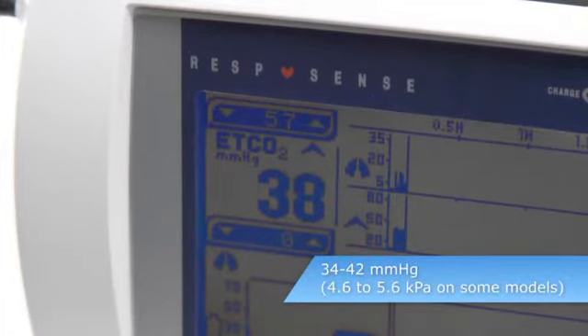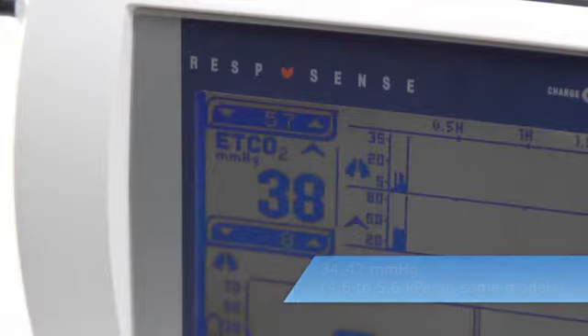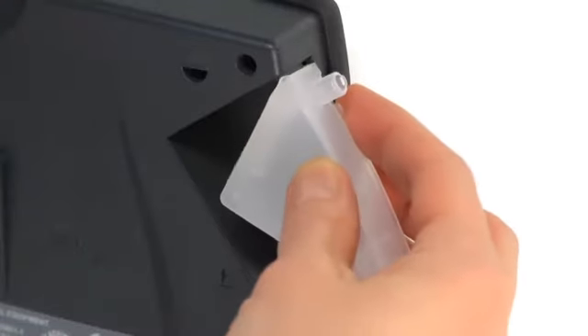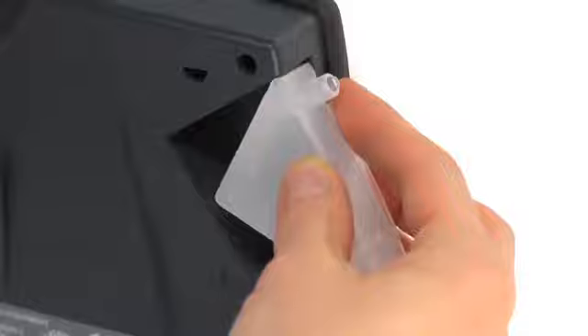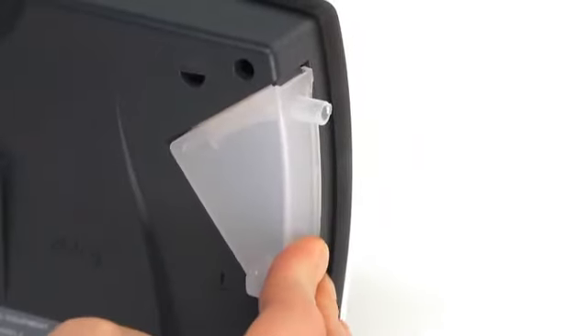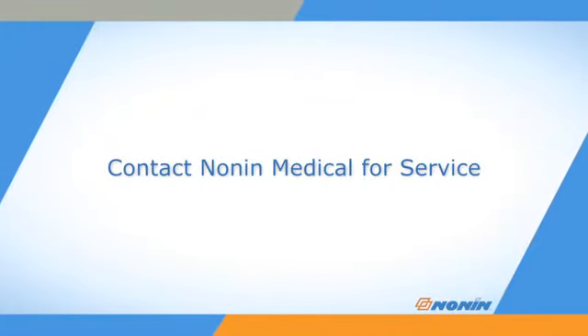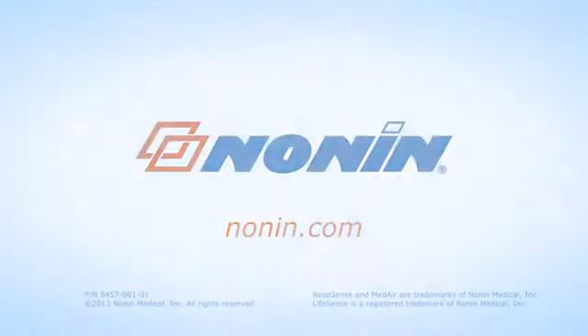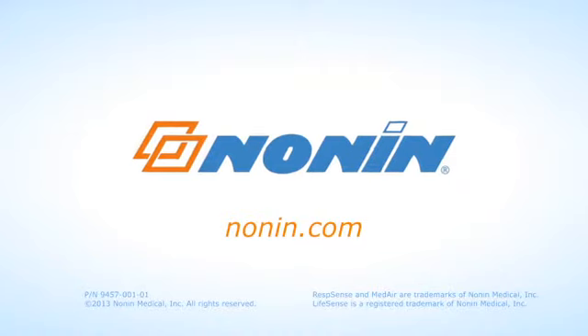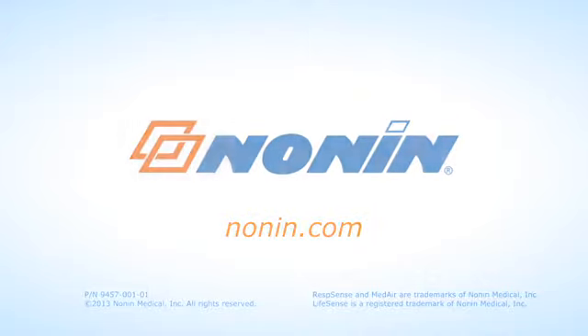The ET CO2 reading should be between 34 and 42 millimeters of mercury. If the reading is out of range, install a new moisture trap and filter set and reattempt calibration and verification. If readings remain out of range, remove the monitor from use and contact NONIN Medical Technical Services for assistance. You can find additional use information on this and other NONIN products at www.nonin.com.